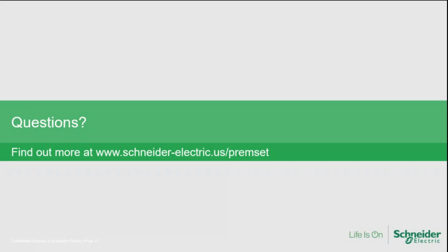What are the BIL and short circuit withstand differences between 15 kV AIS and SIS? With 15 kV AIS, the BIL levels are going to be the same, because BIL is a rating that's associated with voltage class. So at 15 kV, according to the metal enclosed standards, the BIL level of the switchgear needs to be 95 kV BIL. The only place I see a discrepancy in this is when we get into the 38 kV, because there are some requirements from some customers to go beyond what's recommended in the ANSI IEEE standards.